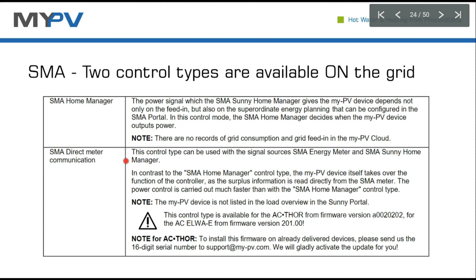Therefore we have a second communication setting for SMA, which offers another way to communicate. The advantage with the SMA direct meter connection is that we control the power output very fast and very accurately, one time per second for each single watt. The balance in the feed-in point is ensured by my-PV. So if you just switch on the light in your living room, we will immediately reduce the power output to ensure the balance in the feed-in point again. So this is the advantage here.